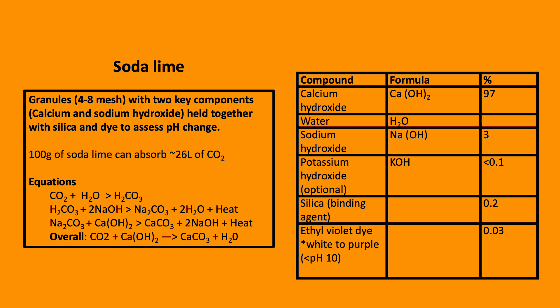It is composed mainly of calcium hydroxide, 97%, but also sodium hydroxide, 3%. The granules are held together with silica and contain a dye that changes colour when the soda lime reaches its carbon dioxide absorbing capacity.